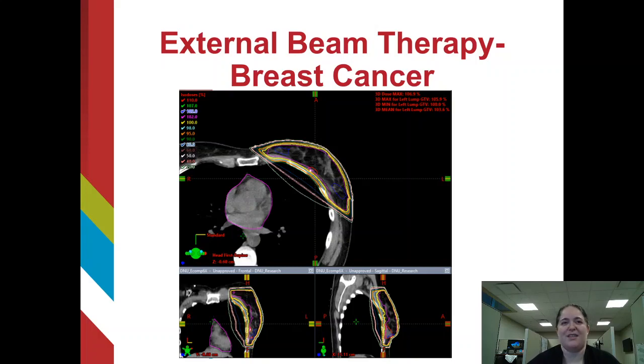The LINAC is built with modifiers that help us shape our outgoing radiation beam. One of those modifiers is a flattening filter, which acts exactly as you'd expect — it flattens our beam. Traditionally, this is favorable to deliver a homogenous dose to a large target in the most efficient manner. Imagine I asked you to draw a straight line. It'd be pretty helpful if I gave you a straight ruler, right? That flattening filter is our straight ruler.